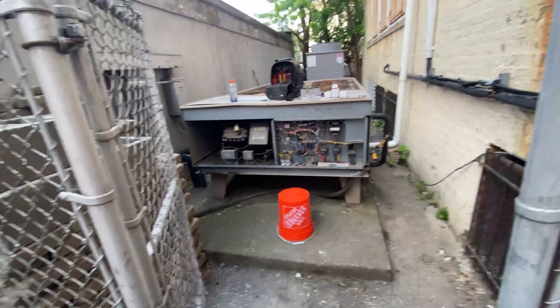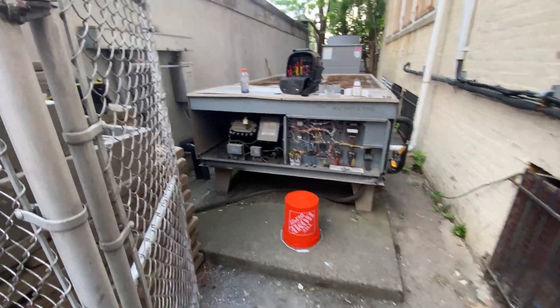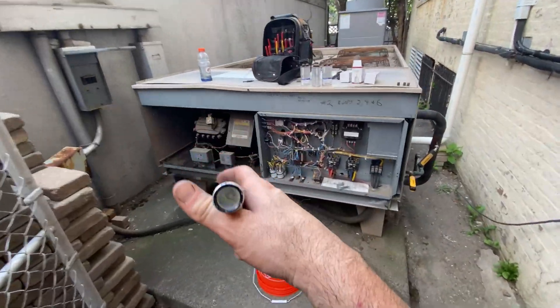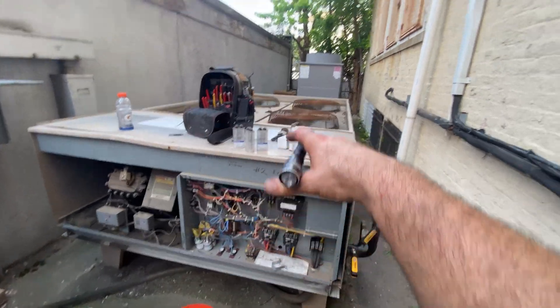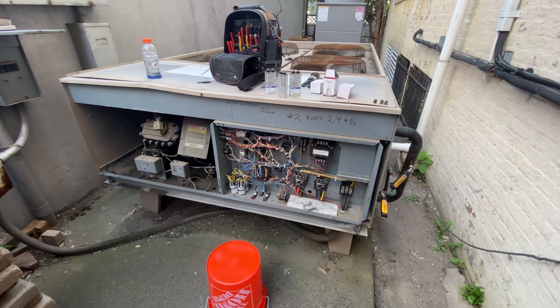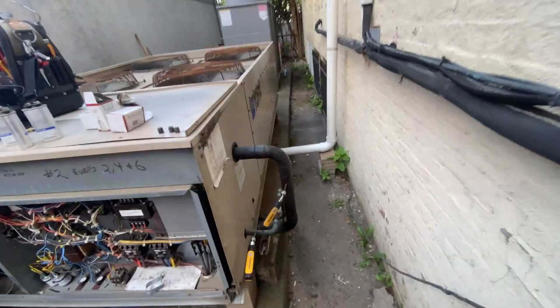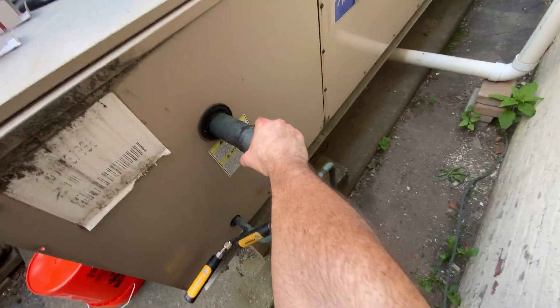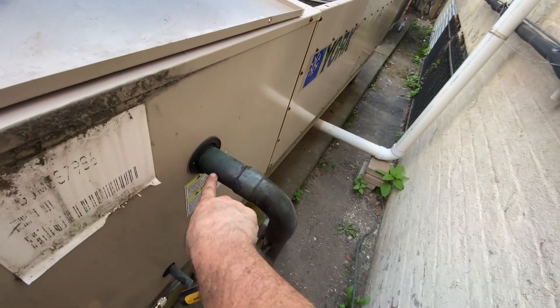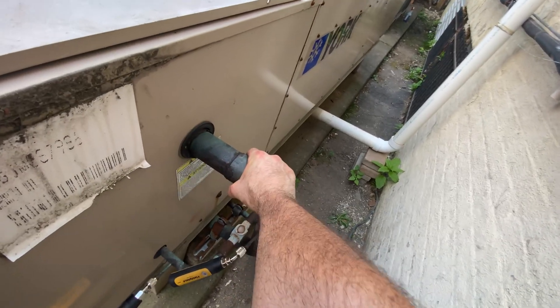This is why I don't make a lot of videos like I used to — this is the kind of stuff I work on. A nice hermetic, a semi-hermetic with three bad caps, condenser fans were off. This thing was overheating and not cooling inside. Now it's working like a champ. Check this out — a beautiful refrigerant charge. We got beer-can cold, it's sweaty, 90-degree day, you got some sweat on it — good charge.